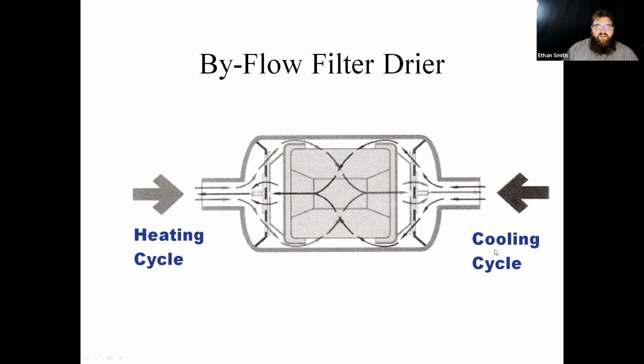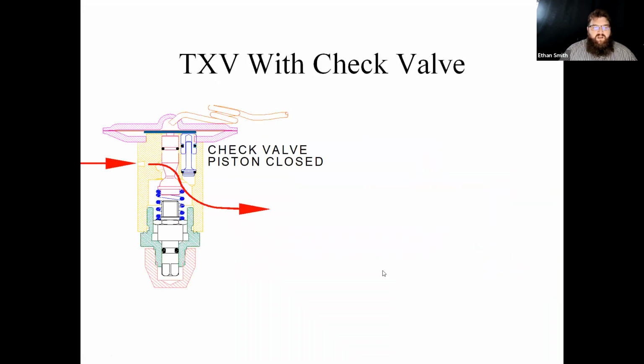If you by chance install a non-biflow filter dryer onto a heat pump, what will happen is it'll work great in one mode, and in the other mode, you'll stack pressure on one side of the system or the other. It just won't allow anything through because of that check valve. TXVs also, more and more, we're seeing TXVs with built-in check valves. We almost never see an external check valve on a coil anymore. Basically, in the heating mode, it just allows it to bypass the metering portion of the valve.